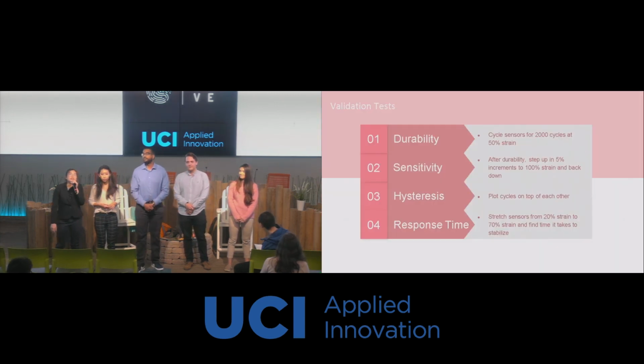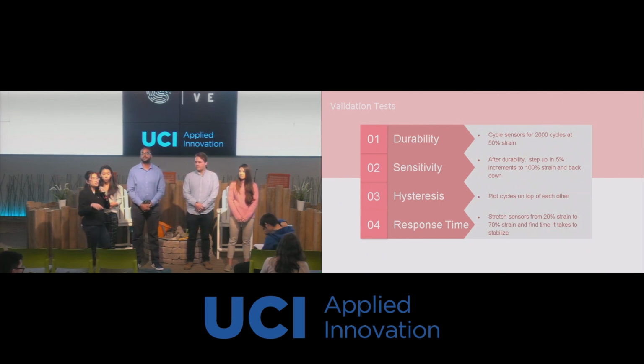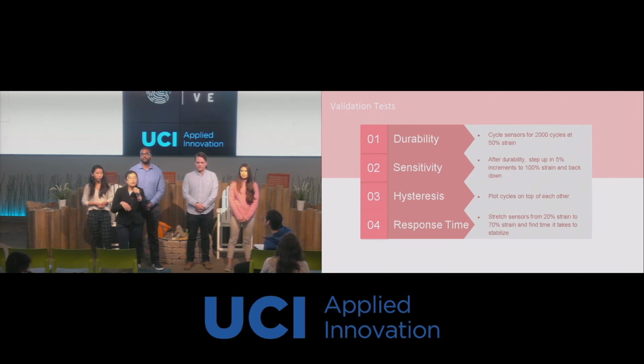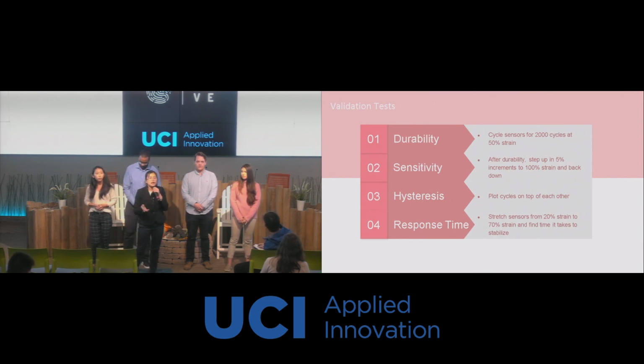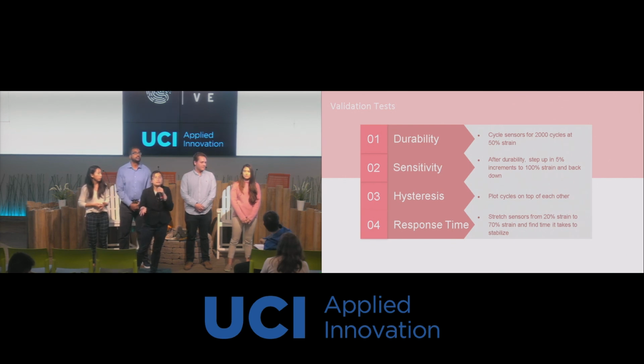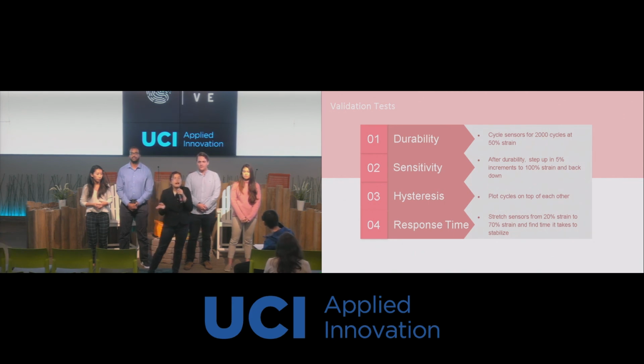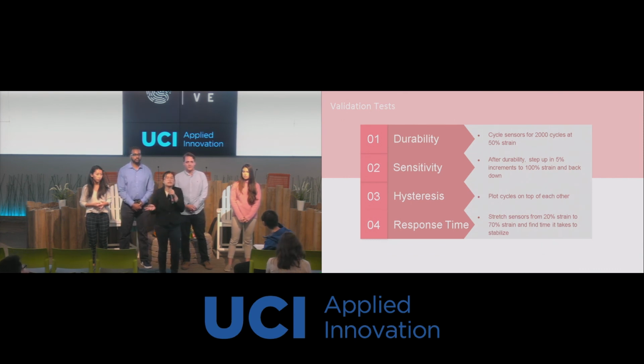So we have a few validation tests to ensure that our device is up to par. One is durability, which would ensure that the lifetime of our device meets the acceptable criteria. And then there's sensitivity, to ensure that the device is picking up on the baby's breathing rate. We're also removing hysteresis by plotting the cycle graphs on top of each other to get an average. And there's a response time test to ensure that our device has a response time under 0.7 seconds.